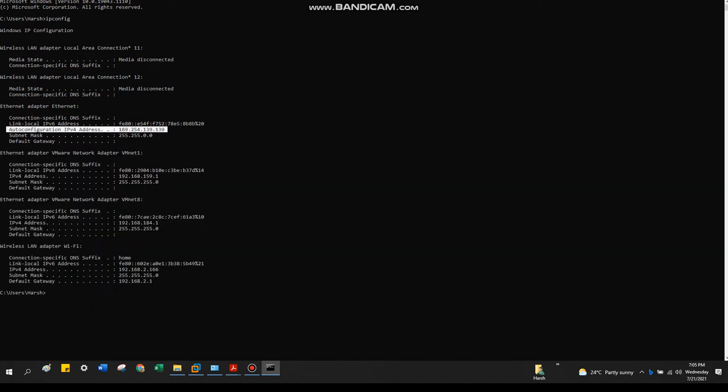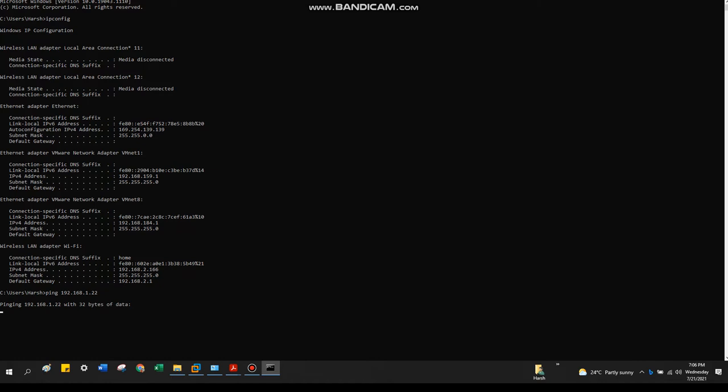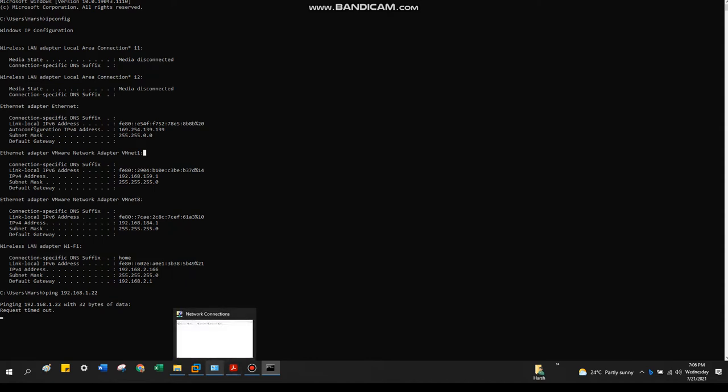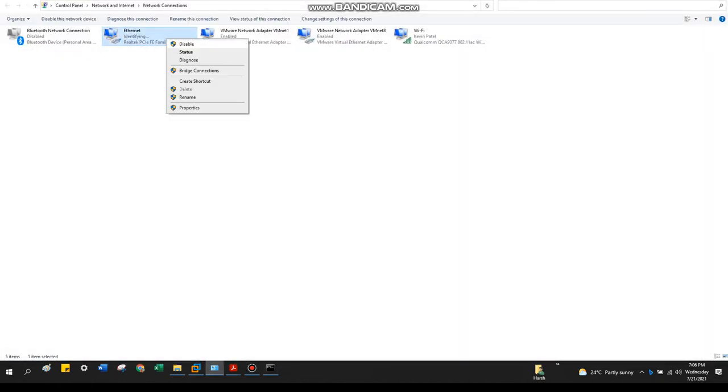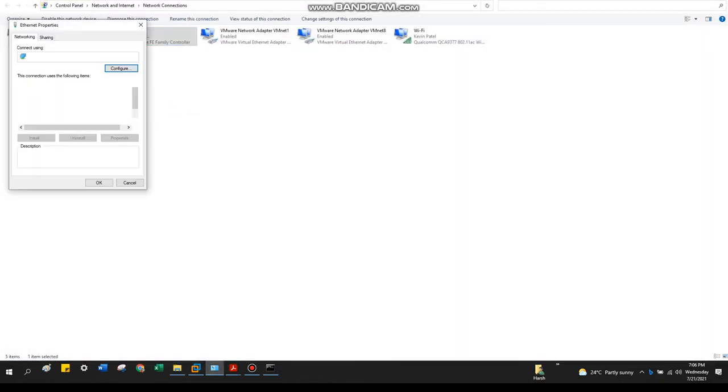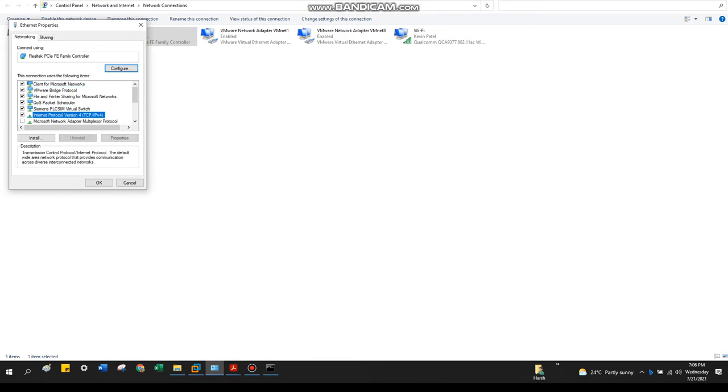So it is on a different series and my PLC IP address is 192.168.1.20. Let's ping it. Yeah, it's not pinging because it's conflicting with the digits, you see. So we need to set this as 192.168.1 and the last octet would be anything other than 20, within 0 to 254. So let's set this. Go to properties, go to TCP/IP v4.